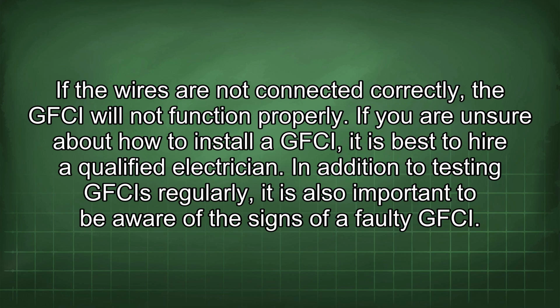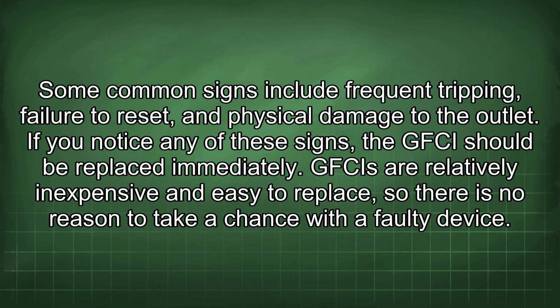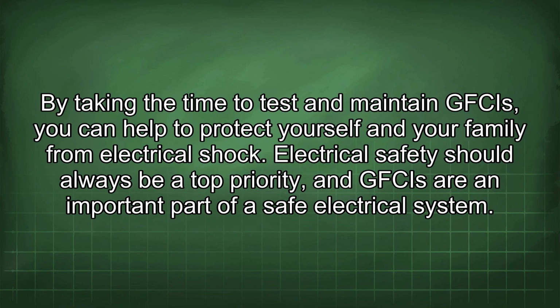In addition to testing GFCIs regularly, it is also important to be aware of the signs of a faulty GFCI. Some common signs include frequent tripping, failure to reset, and physical damage to the outlet. If you notice any of these signs, the GFCI should be replaced immediately. GFCIs are relatively inexpensive and easy to replace, so there's no reason to take a chance with a faulty device. By taking the time to test and maintain GFCIs, you can help to protect yourself and your family from electrical shock. Electrical safety should always be a top priority, and GFCIs are an important part of a safe electrical system.